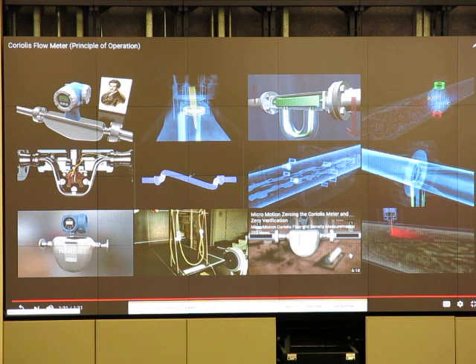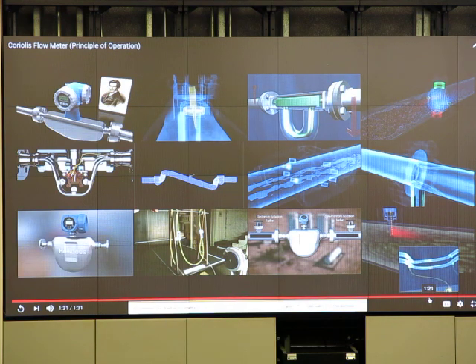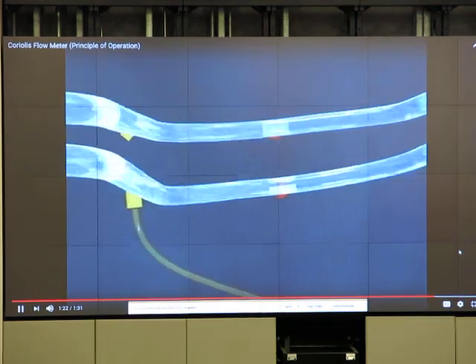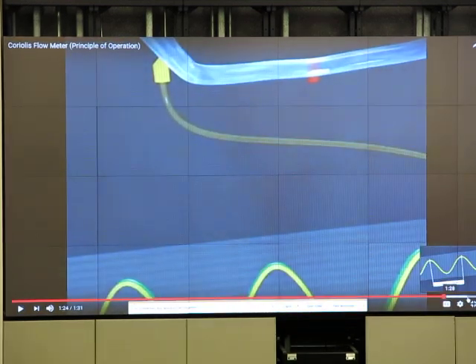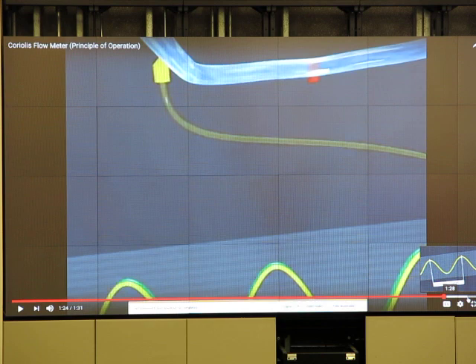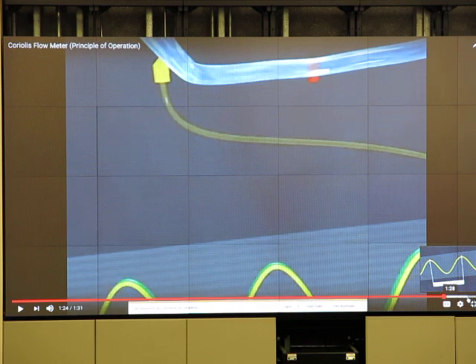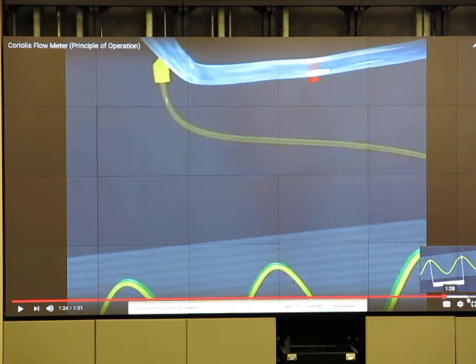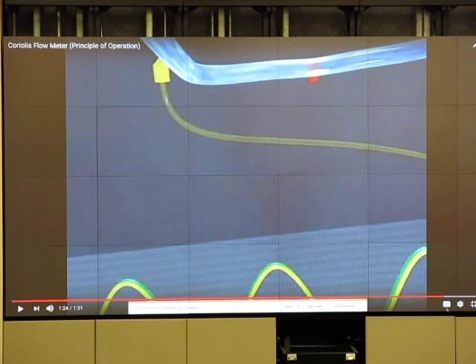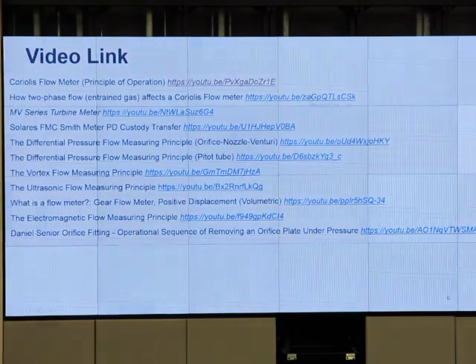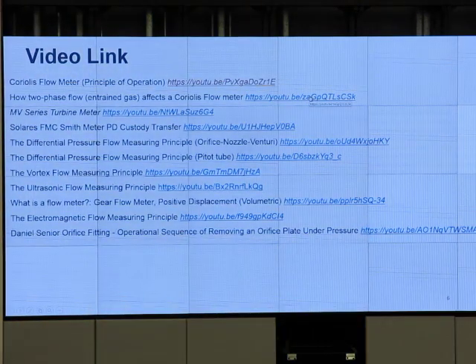Density is measured from how fast the tubes oscillate (oscillation frequency). Mass flow rate is measured from the phase shift between the two sensors. When there's no flow, everything oscillates at the same frequency. When something flows inside, a phase difference occurs. Make sure you can explain the working mechanism of the Coriolis flow meter.